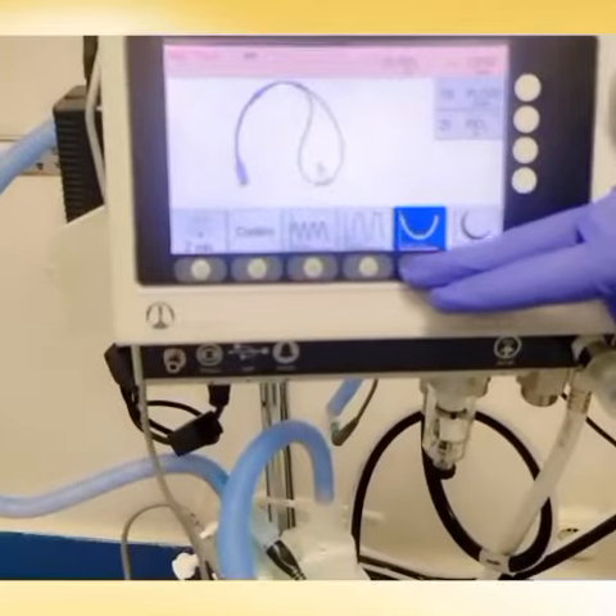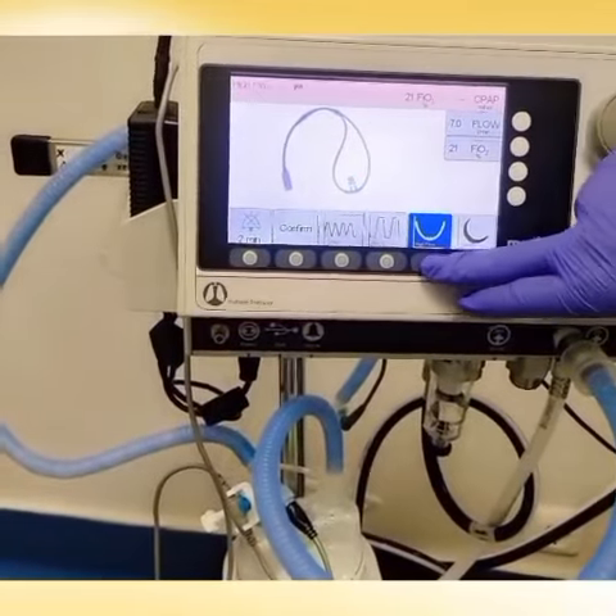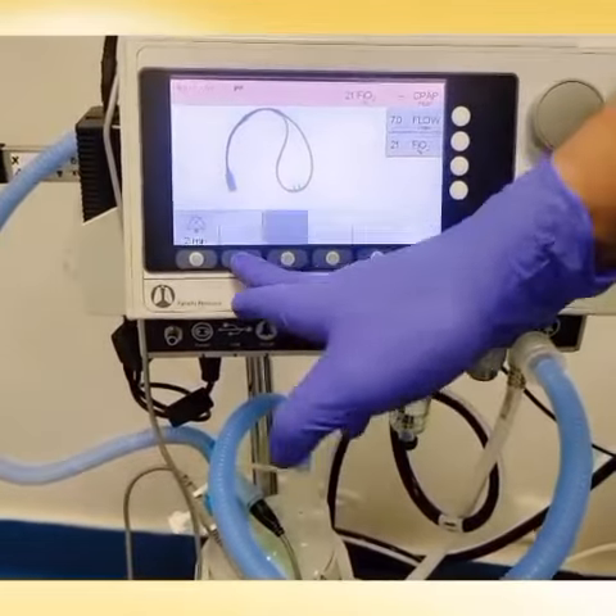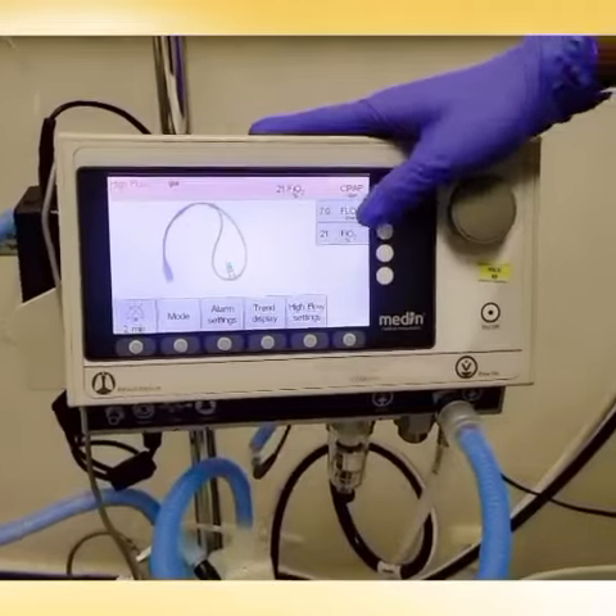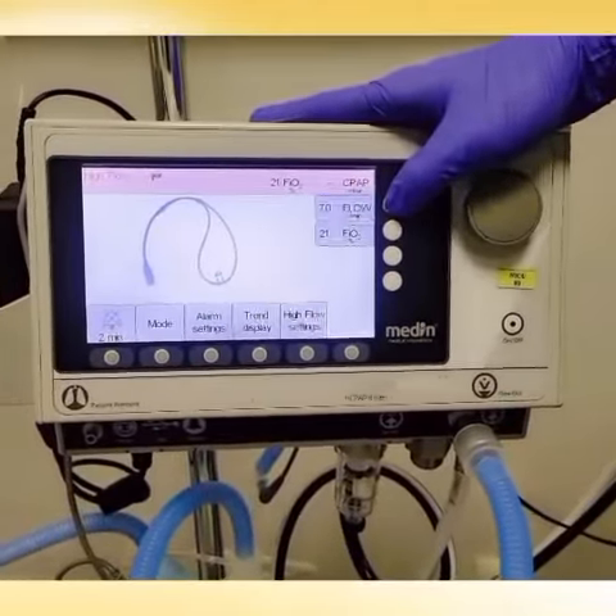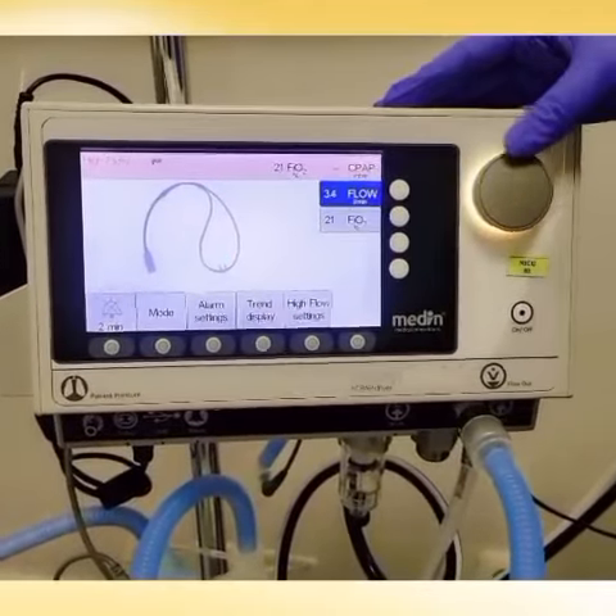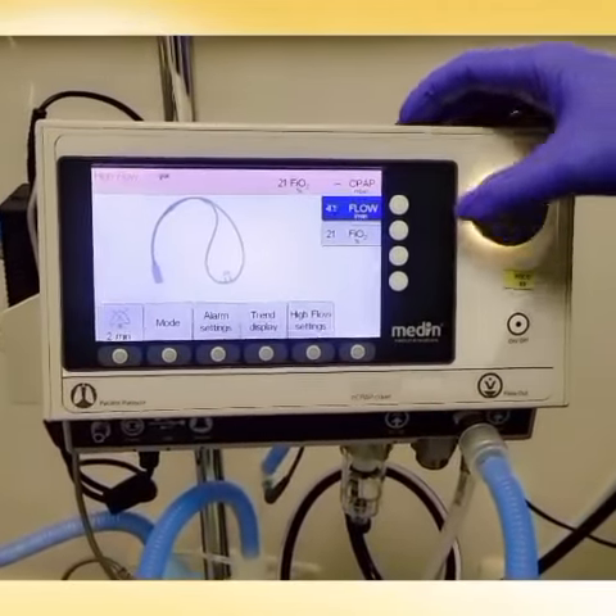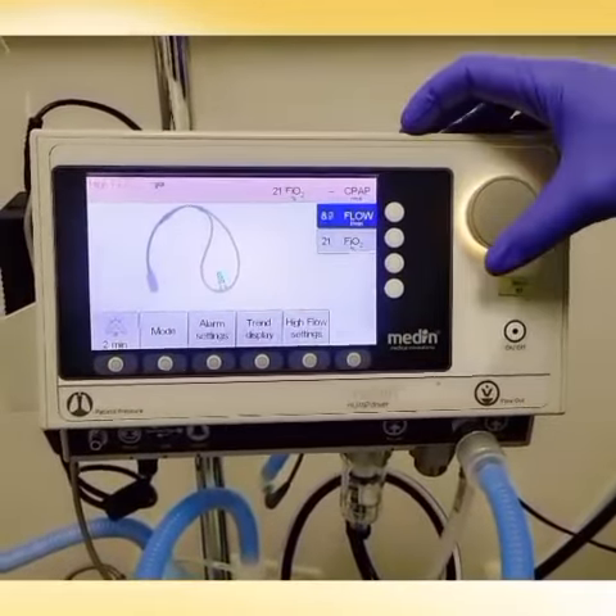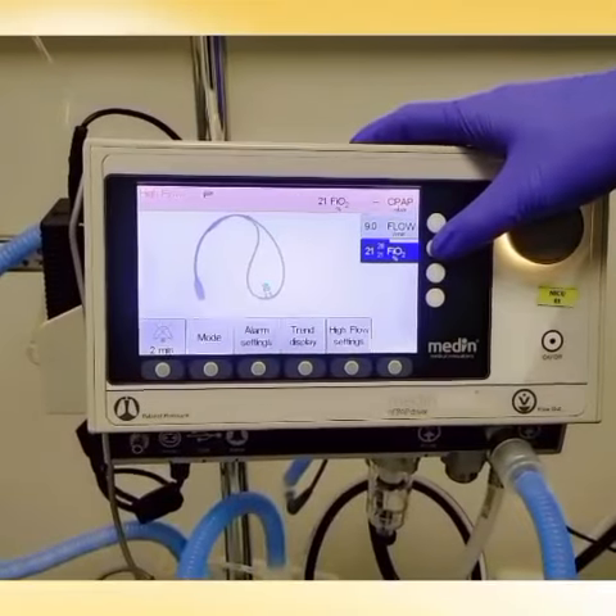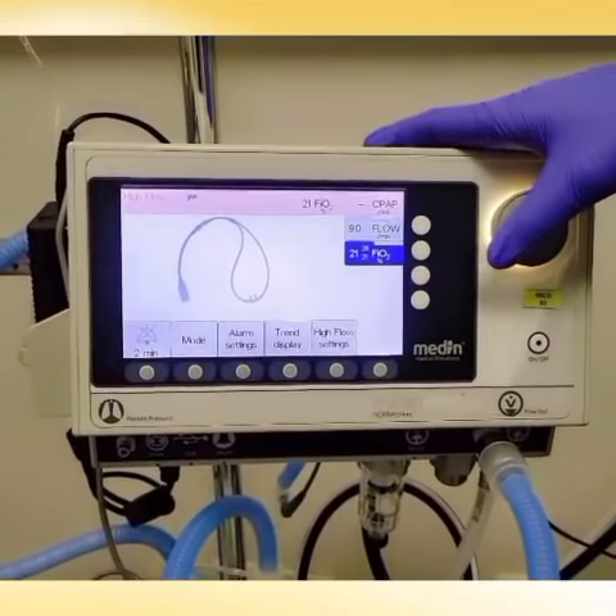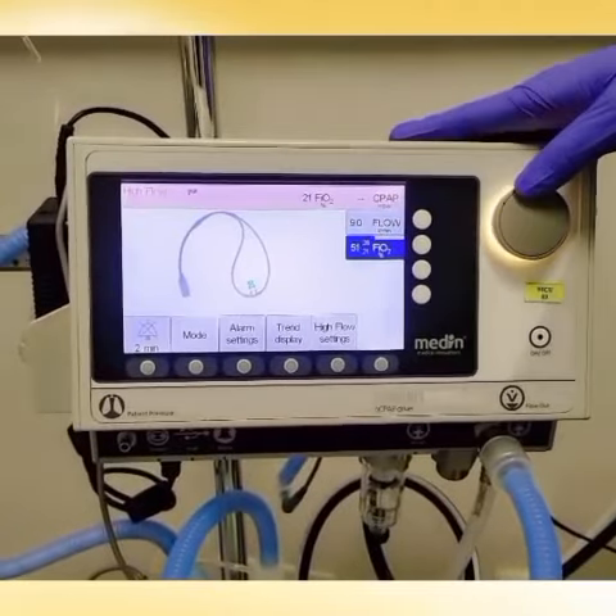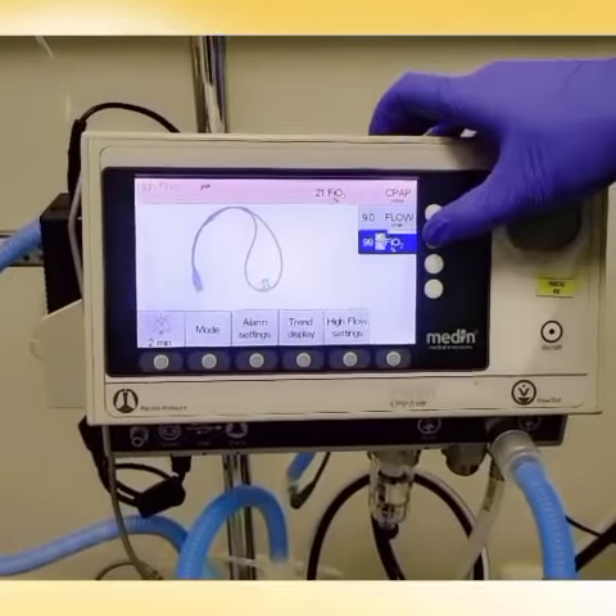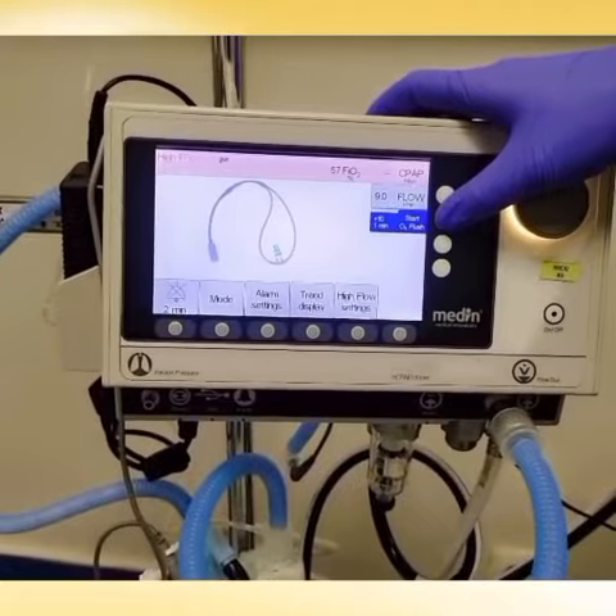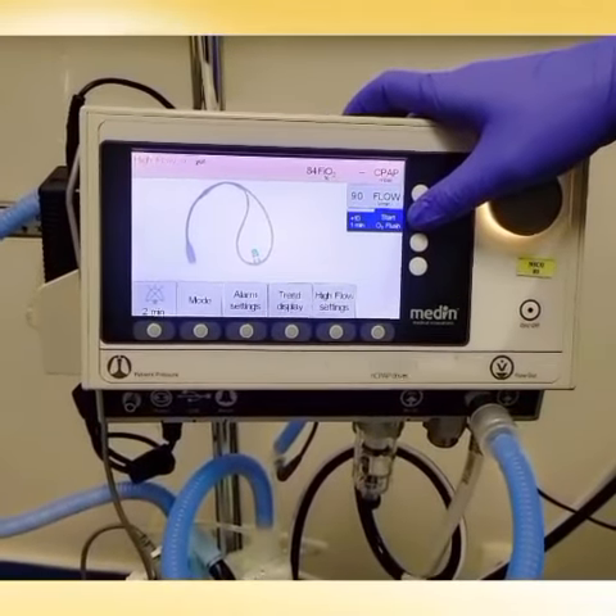Here we have the high flow nasal cannula mode. We select the mode from this button and then confirm it from this one. Okay. Now, as you can see here, here's the option for the flow. We can adjust it with this knob. It starts from 0.1 liters per minute to a maximum of 12 liters. We adjust it as per the patient's need. And the second one is FiO2, fraction of inspired oxygen, that we adjust from 21 to a maximum of 100%.